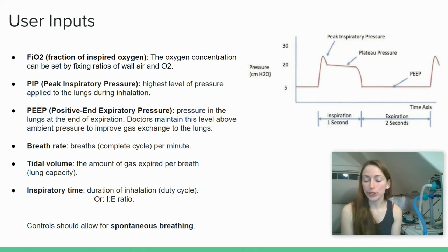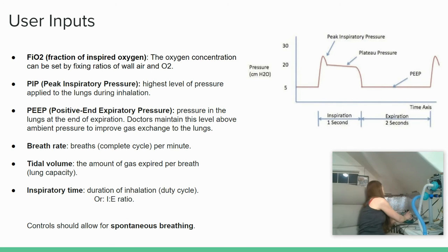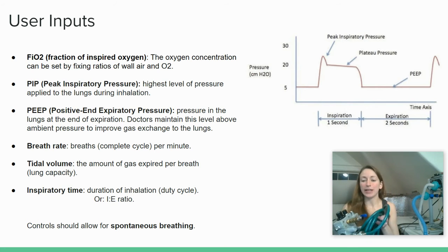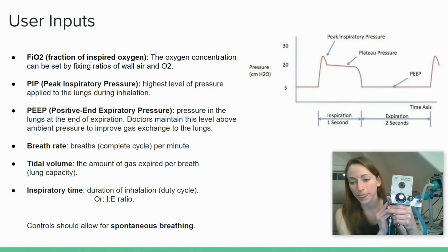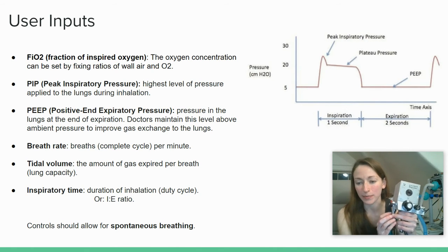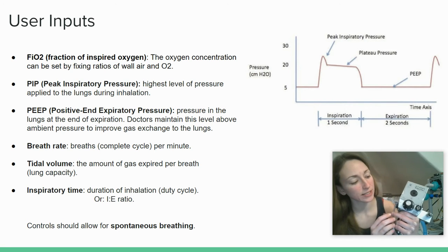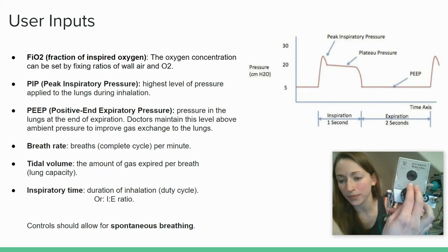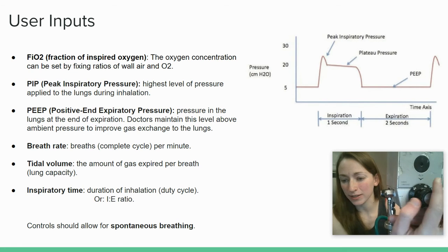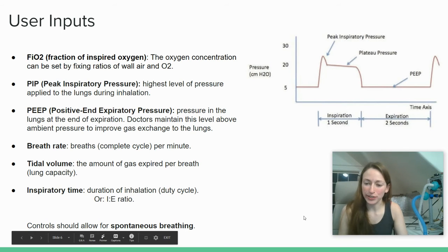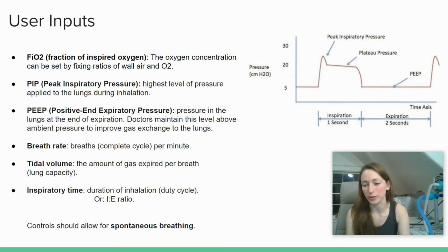At least for our design, we're assuming that at the wall of the hospital there's something like a gas blender. I have an older medical gas blender here. It looks something like this. Normal air on its own has an oxygen concentration of 21%, and so these settings go all the way from 21% all the way up to 100. Okay? Under different settings, maybe in field hospitals, you may be working with oxygen canisters and compressed air, but for now we're assuming that we have this gas blender solution.